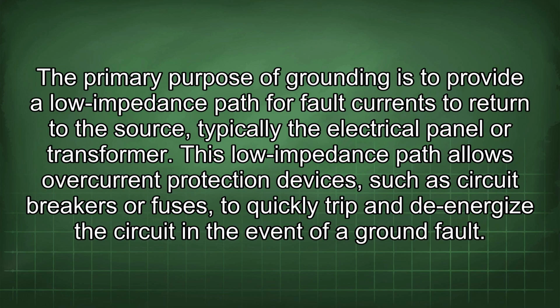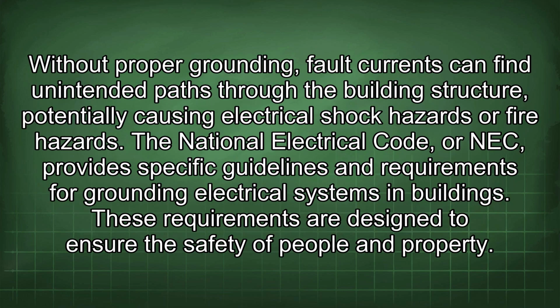The primary purpose of grounding is to provide a low impedance path for fault currents to return to the source, typically the electrical panel or transformer. This low impedance path allows overcurrent protection devices, such as circuit breakers or fuses, to quickly trip and de-energize the circuit in the event of a ground fault. Without proper grounding, fault currents can find unintended paths through the building structure, potentially causing electrical shock hazards or fire hazards.